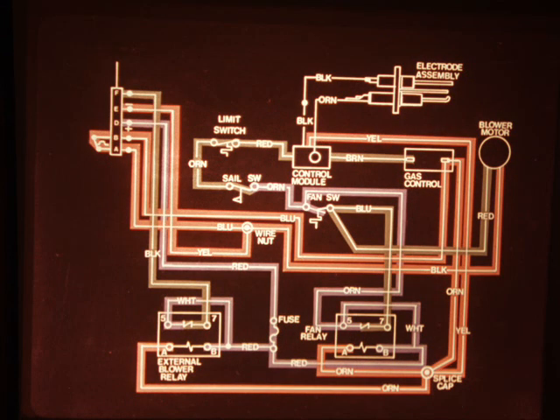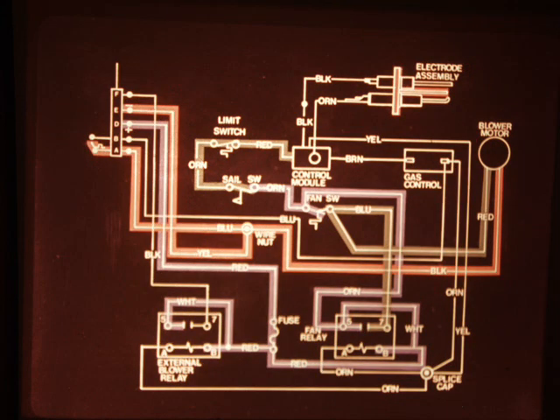After a minute or so, you'll hear the snap as the fan switch heats up and closes. This provides a second path of current flow to the furnace blower motor. The furnace will continue to run in this mode until the thermostat is satisfied or turned down to a lower setting. When this happens, current flow to the solenoid stops, the valve closes, and the burner flame goes out. The auxiliary blower shuts down. With the fan switch closed, the furnace blower continues to run. It shuts down when the switch cools and the switch contacts open. The furnace is now shut down until the thermostat again calls for heat.